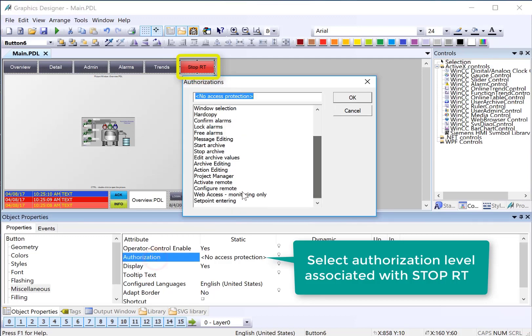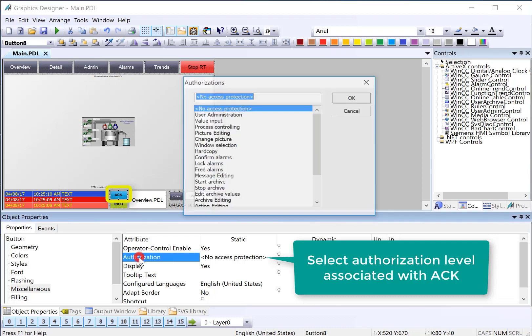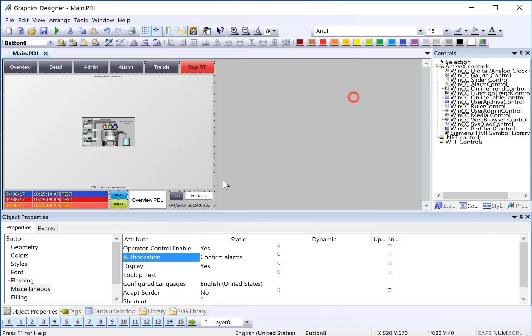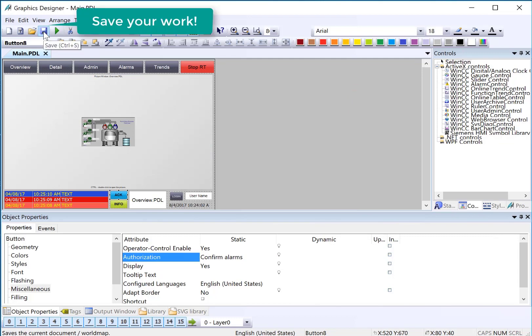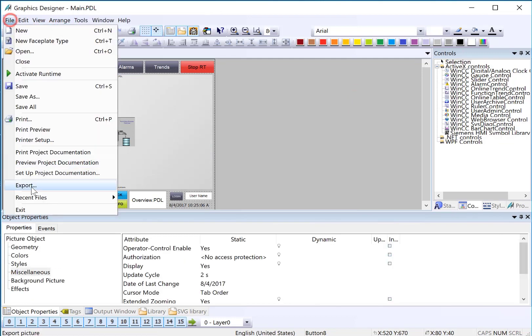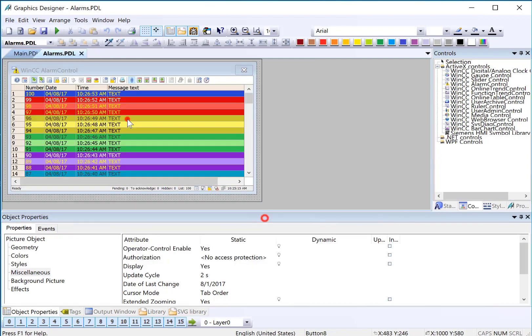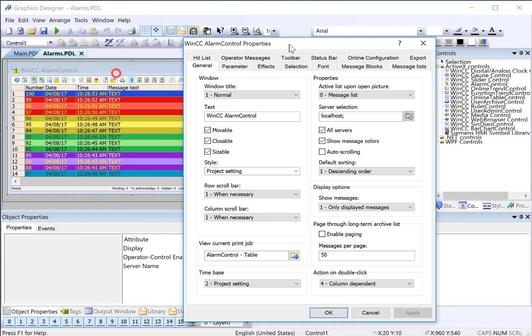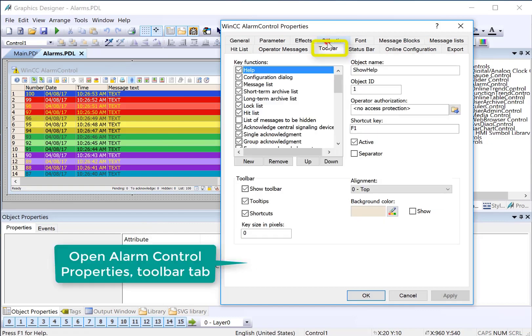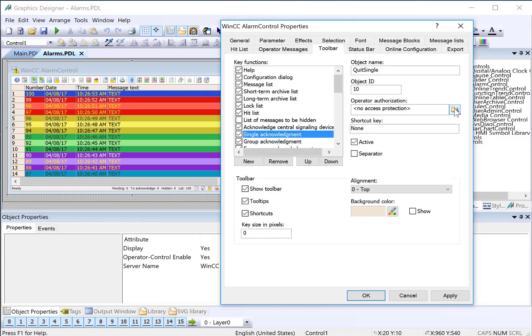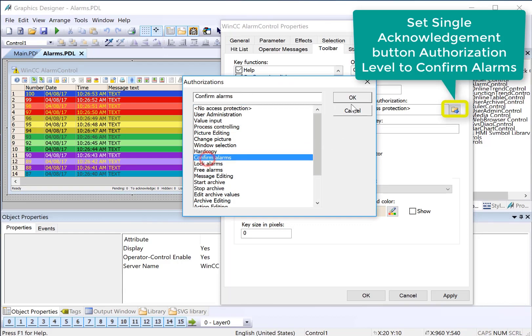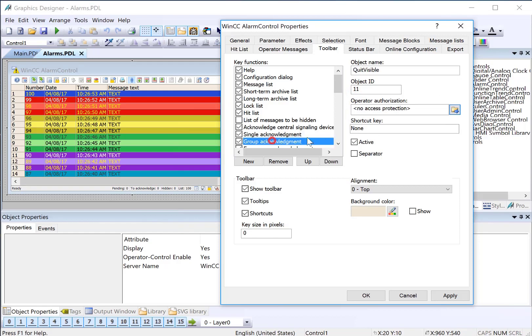To stop runtime we will use project manager. And then for our acknowledgement button we will use confirm alarms and click Save. Next we will open our alarm screen and we'll double click to access the properties of our alarm control. We can assign authorization levels directly to buttons on the toolbar so we will do confirm alarms for single acknowledgement as well as group acknowledgement. Click OK, save.